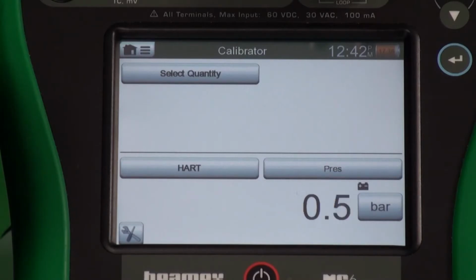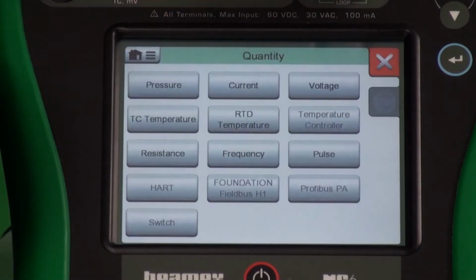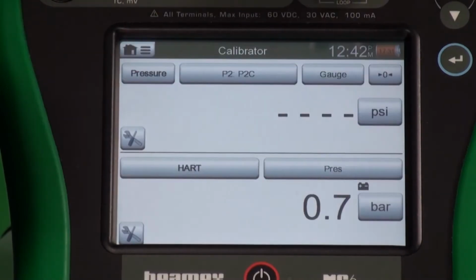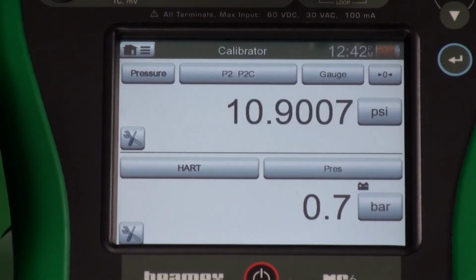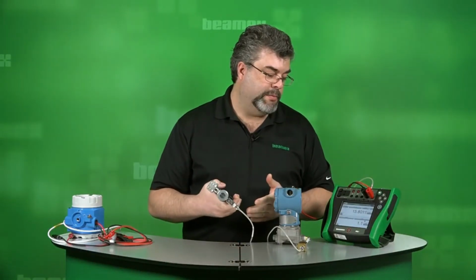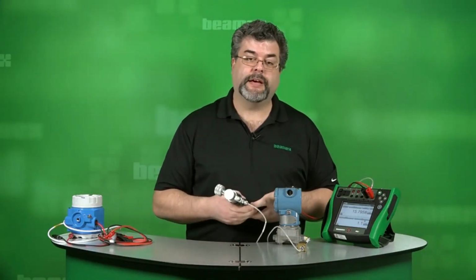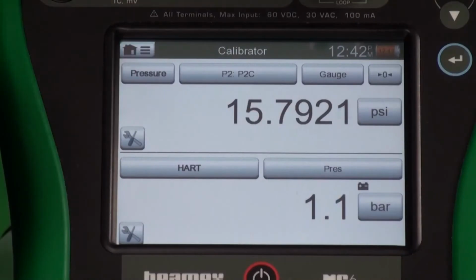We can see a difference happening with our pressure. If we want to, we can select the quantity up here on the top and have the calibrator actually measure as well. So we'll pick pressure. Now we have a difference here. The bottom one, I'm sitting at 1 bar, but on the top I've got it registering in PSI. Let me just change this.